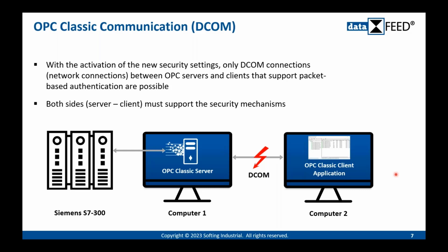And in this case, both sides, server and client, must now support the security mechanism because otherwise they are no longer able to communicate. So, as a reminder, only communication between two separate computers via this Microsoft DCOM technology is affected by this Microsoft security update.